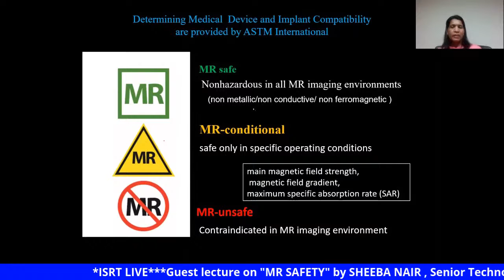MR safe means mostly these materials will be non-metallic, non-conductive, and non-ferromagnetic, and they are non-hazardous in all MR imaging environments. MR conditional means they are safe only under specified operating conditions. The specification will be in terms of magnetic field strength, magnetic field gradient, or the specific absorption rate. For example, if a device is labeled conditional at 1.5 Tesla, it will be safe at 1.5 Tesla. It will not be safe for 3 Tesla imaging.